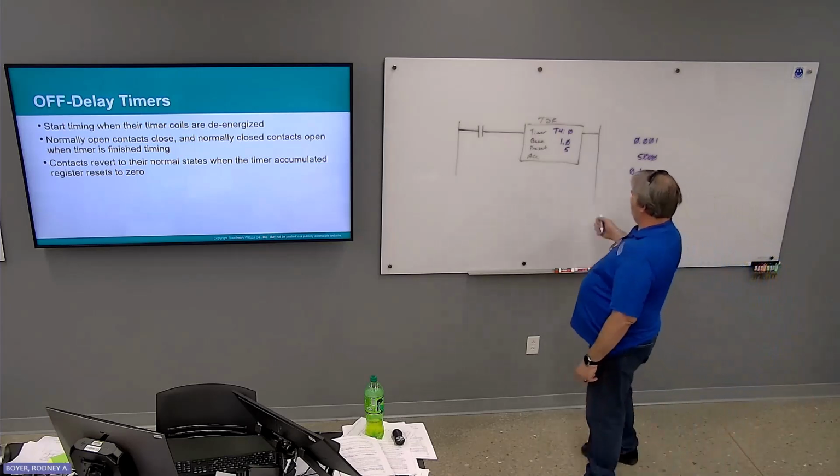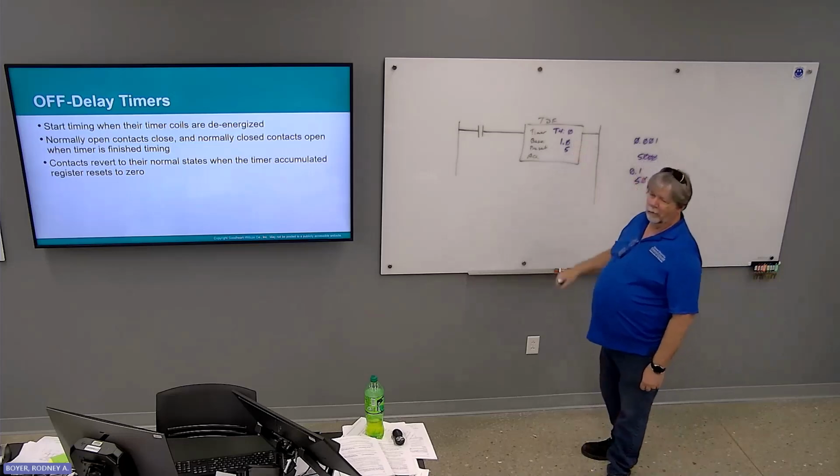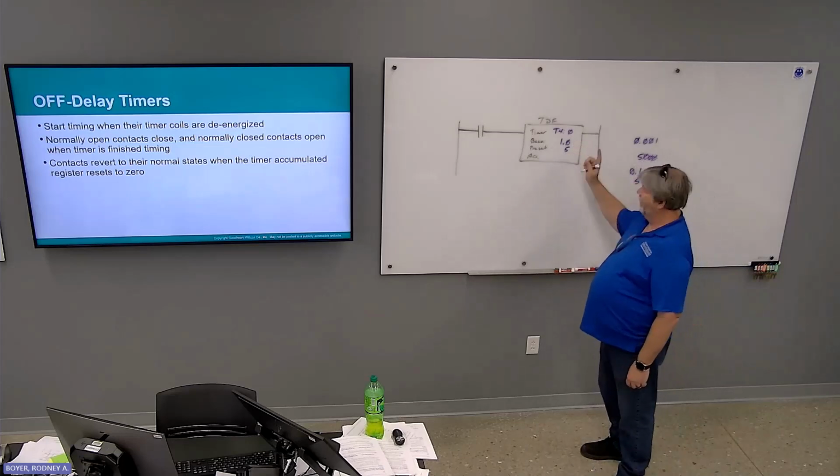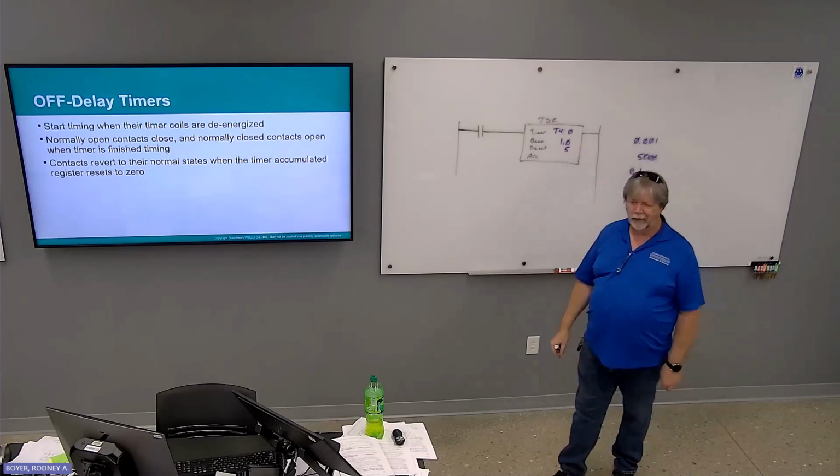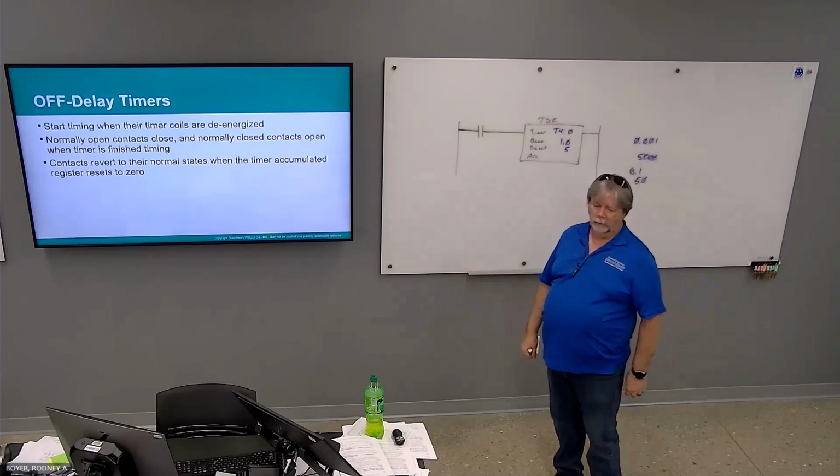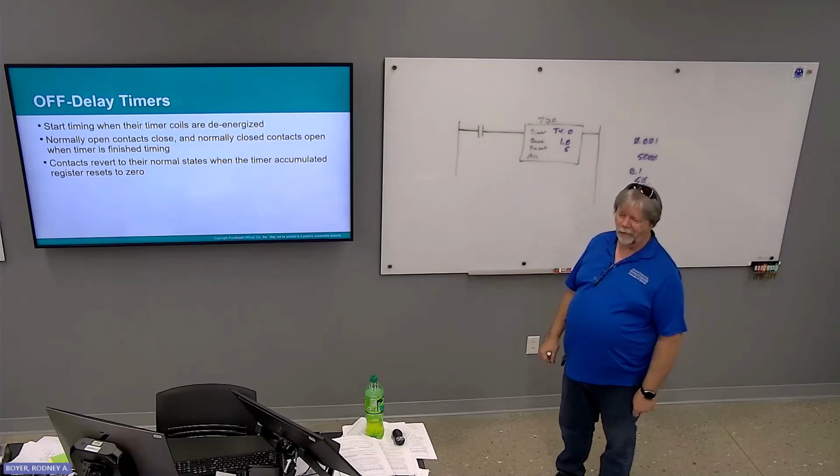Where people get hung up is they set their base wrong, and then they put 1/10 of a second, put 5, and well, it's not 5 seconds. Why not? Read your logic. It'll tell you every time.